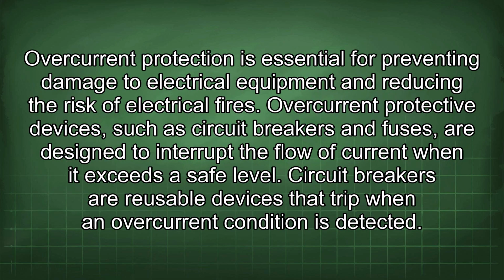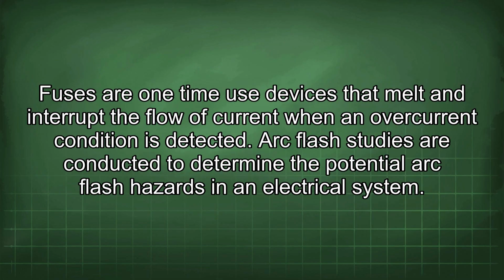Overcurrent protection is essential for preventing damage to electrical equipment and reducing the risk of electrical fires. Overcurrent protective devices, such as circuit breakers and fuses, are designed to interrupt the flow of current when it exceeds a safe level. Circuit breakers are reusable devices that trip when an overcurrent condition is detected. Fuses are one-time use devices that melt and interrupt the flow of current when an overcurrent condition is detected.